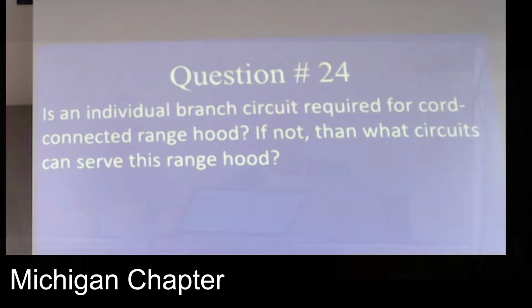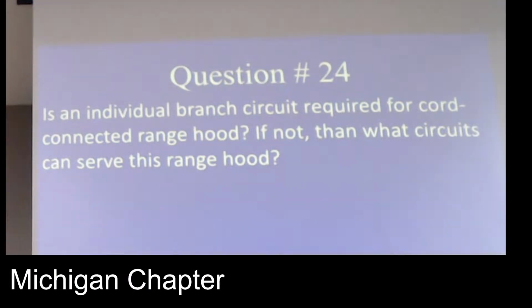In the MRC, the 2015 E4101.3, a receptacle for a cord-and-plug-connected range hood shall be supplied by an individual branch circuit. Says it pretty simply. When you go to NEC 422.16, it talks about range hoods being permitted to be cord-and-plug connected with a flexible cord where all of the following conditions are met. It gives you five conditions, and the last one, number 5, is the receptacle is supplied by an individual branch circuit. So I think that's the answer you're looking for.